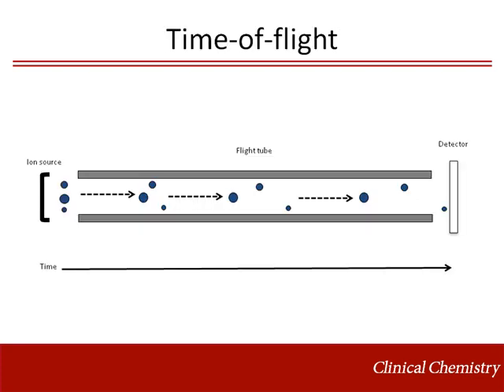Time-of-flight analyzers use an electric field to accelerate bundles of gas phase ions towards the detector. Since all ions are being accelerated by the same electric field, ions with a low mass-to-charge ratio will accelerate faster than ions with a high mass-to-charge ratio. How long it takes a given ion to travel down the flight tube is how ions of different mass-to-charge ratios are distinguished. Time-of-flight analyzers have essentially an unlimited mass-to-charge range, very high sensitivity, very high mass accuracy, high transmission percentage, but a limited dynamic range.